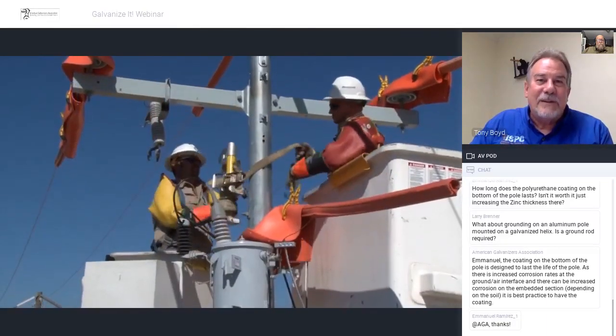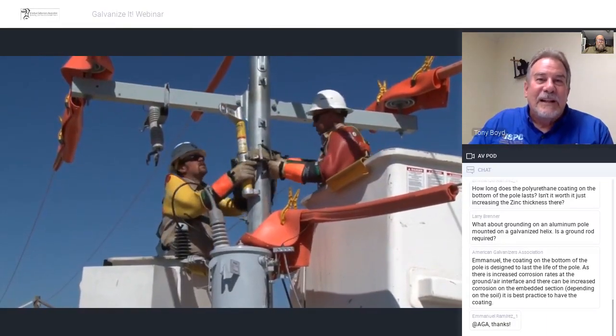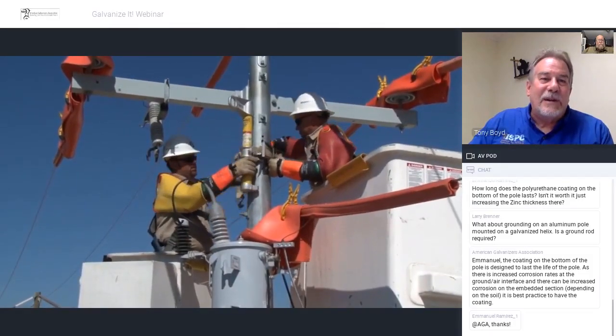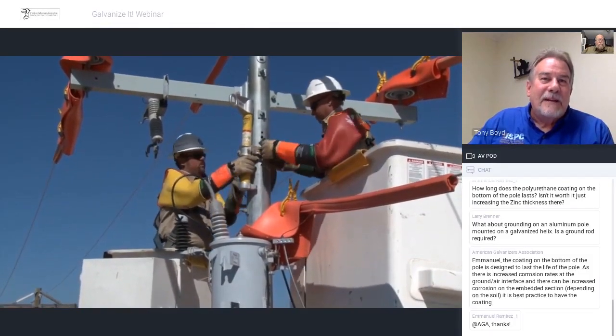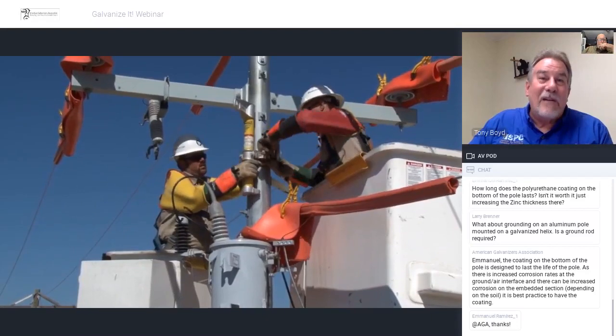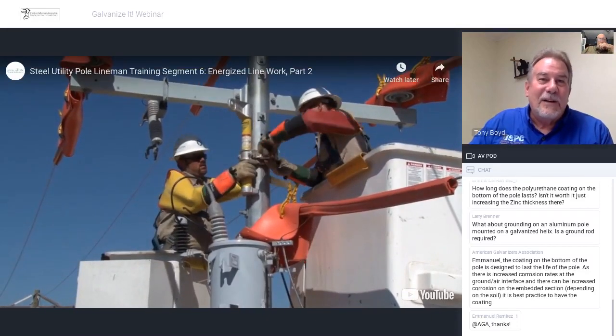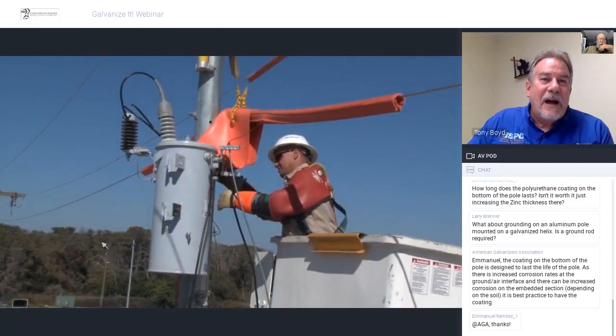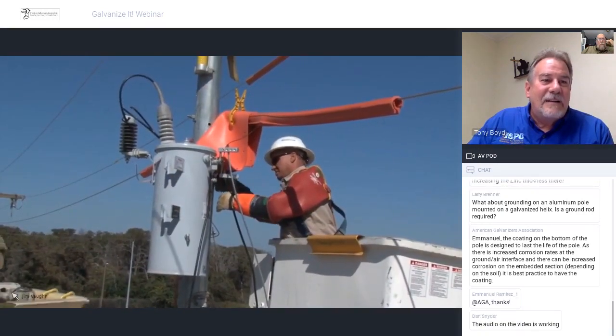Once the primary is rubbered up, the line worker rigs the upper block. So what they're doing here, once the sling is secure, the line worker hangs the block so it's positioned above the transformer. If you don't have a material handler, you use a jib and rope blocks. The secondary leads are disconnected from the transformer's terminals.